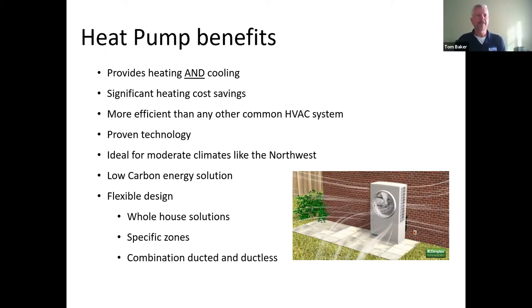Okay. Yeah, the 300% is calculated a little bit differently. To generate heat with a heat source is different than to pump it into your house. You've got duct loss, you've got heat loss through your ductwork, and other things that affect the actual efficiency. So we're not really comparing apples to apples when we talk about that 300%. And keep in mind that that 300% is a low-end figure. If you go into the higher HSPF, which is an efficiency rating, you can get much higher than 300%. So a good question. It's a little confusing and technical, but that's the deal there.